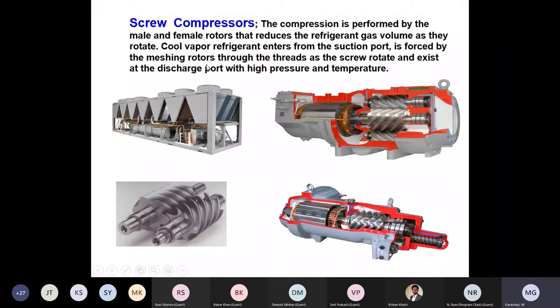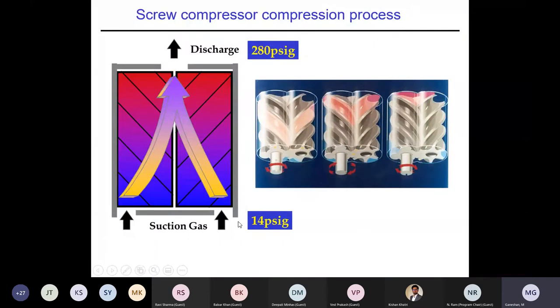Here the compression takes place by meshing these rotors. When the suction gas goes in, by the time it comes out at the end it becomes completely compressed. The suction gas of 14 PSI or 35 PSI, whatever it is designed for in the application, comes in, gets meshed by the rotors, and then goes to the discharge side.